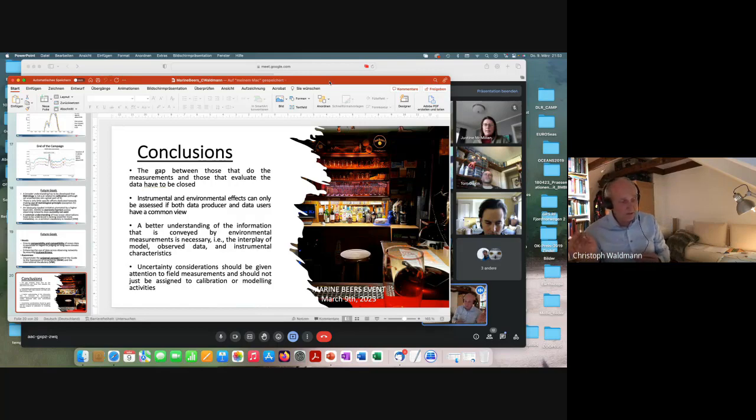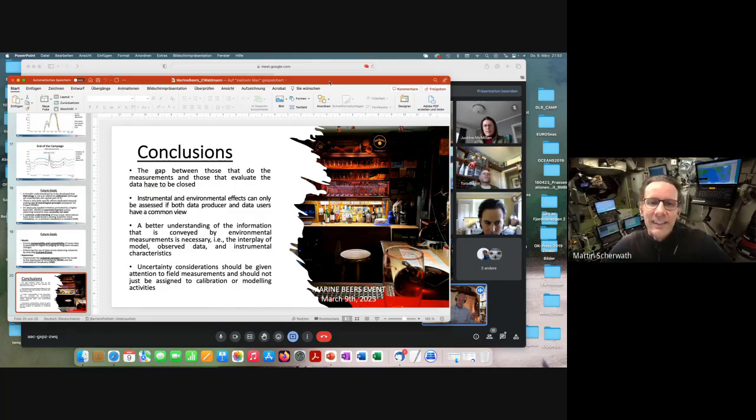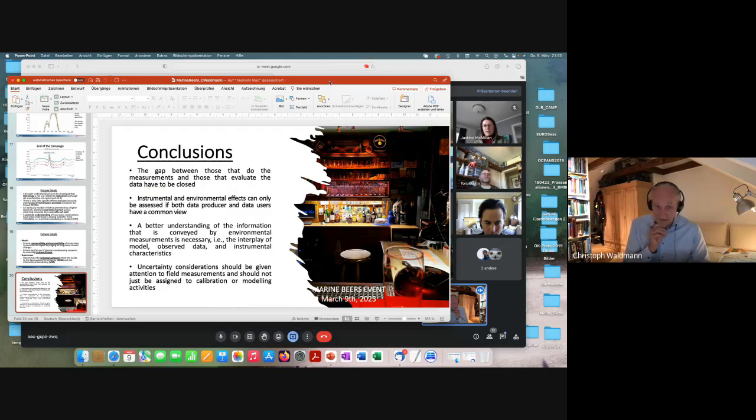And Sea-Bird is recommending a linear approach to that. You take the starting point and the end point, do a post-calibration, and then you do a linear correction on that, assuming that you have a linear effect in regard to drift. You're probably aware of that? Yeah, that makes total sense. Okay, and that's something that I doubt. It will not be linear over time. But that's a very difficult thing.